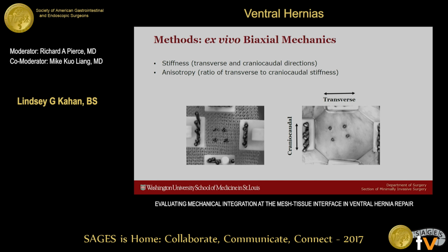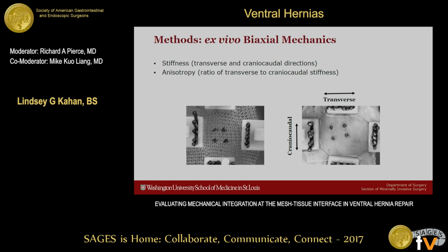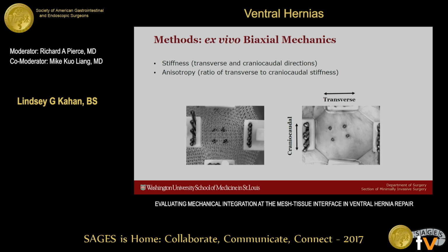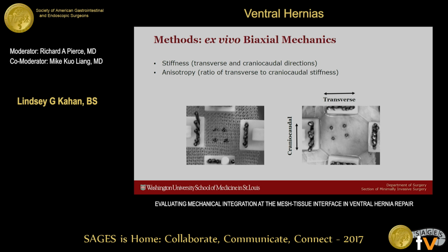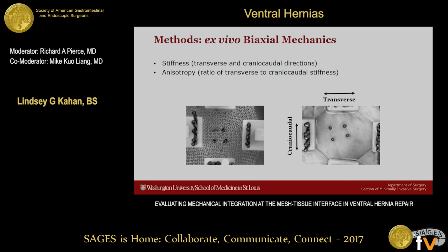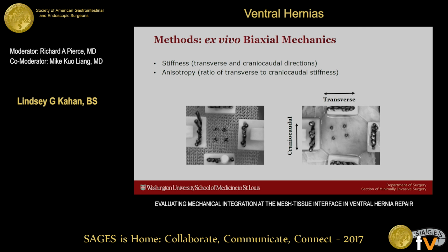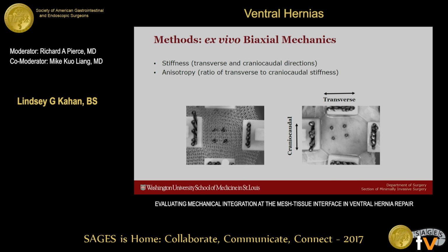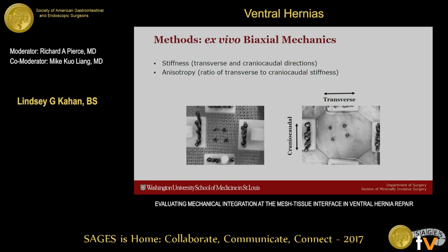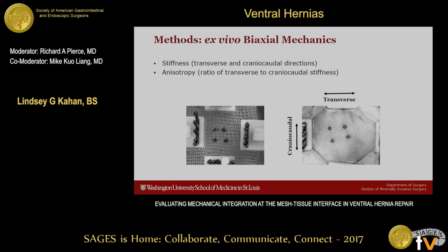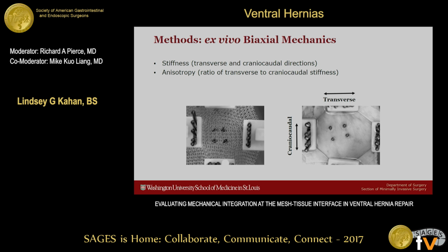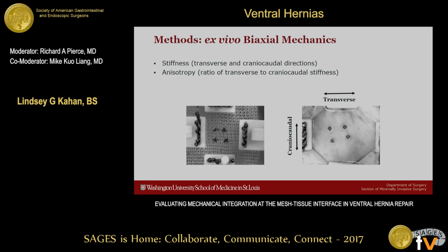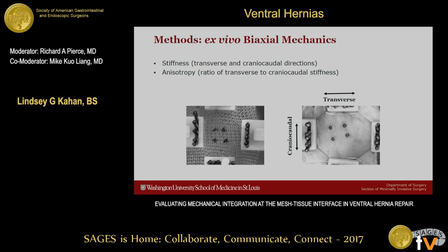So for our ex vivo biaxial testing, we use this biaxial method, or simply testing in two directions, in order to test the stiffness of transverse and craniocaudal. This is a much more clinically relevant test method because in vivo forces and strains really don't occur in just one direction. We also studied the anisotropy, or simply the ratio of stiffness in the transverse versus craniocaudal directions. Now, this test method was for our meshes alone, for native tissue, and for those two treatment groups of ingrown explanted tissue at 28 days.